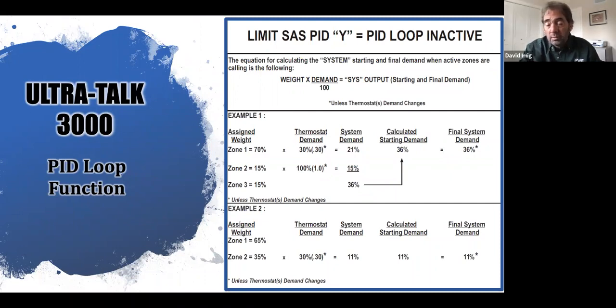And you'll see down below it's 11%. So it means I'm always in first stage as well with either one of those zones. In example 1, I would have to see zone 3 call to get enough weight to take it into second stage, to take it beyond 51%. So only when all 3 zones are calling, which probably means I've got an extreme temperature one way or another at the time, will I have the ability to go into second stage when I'm taking the loop out of the equation.